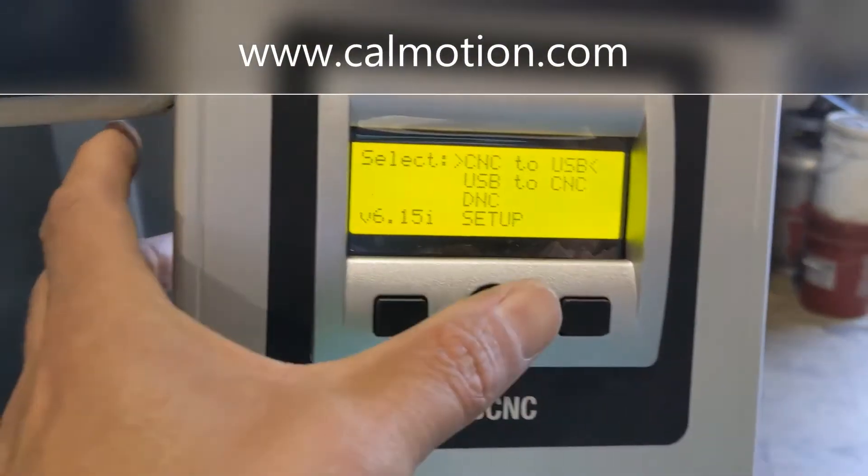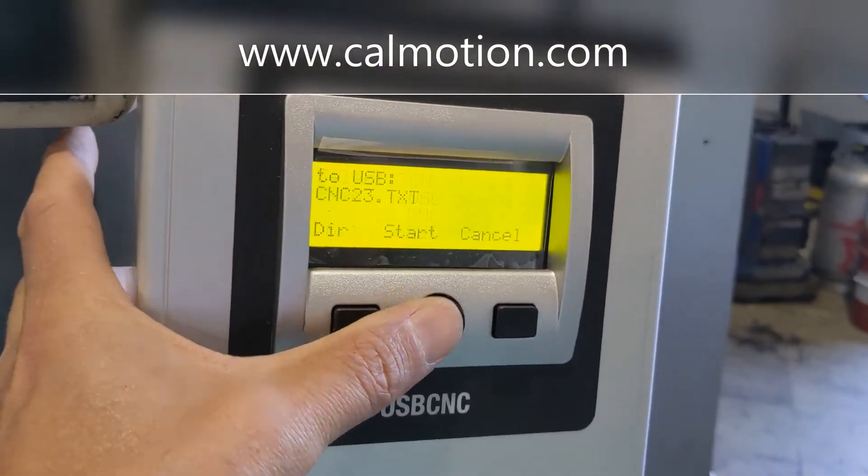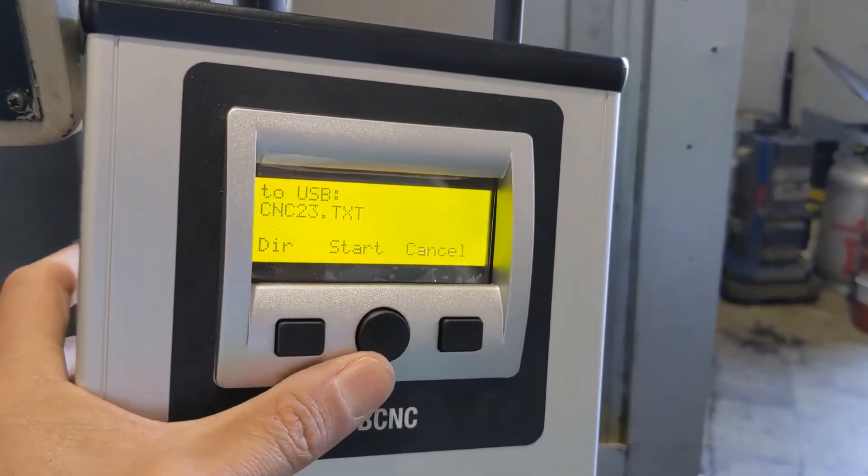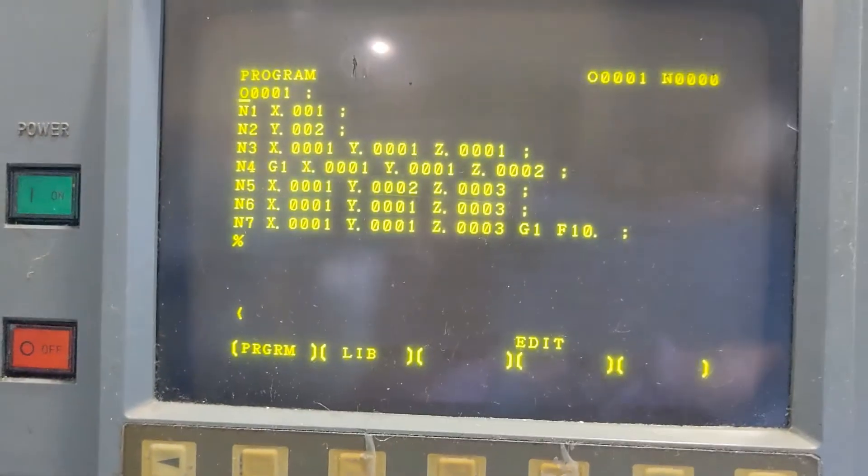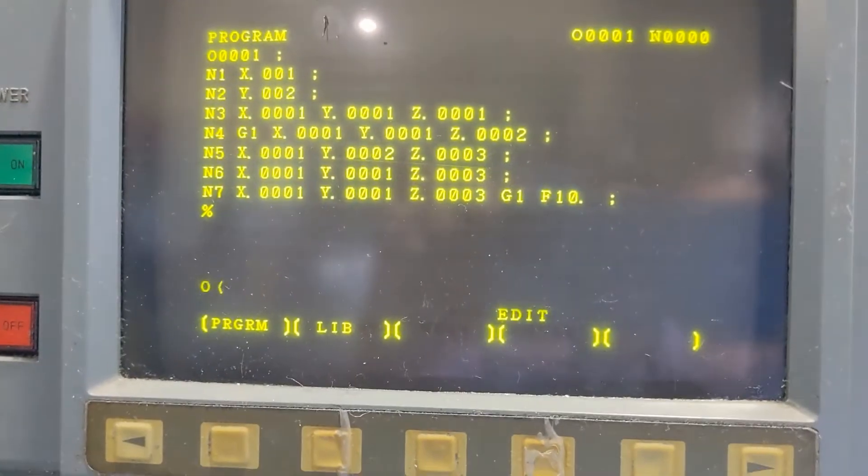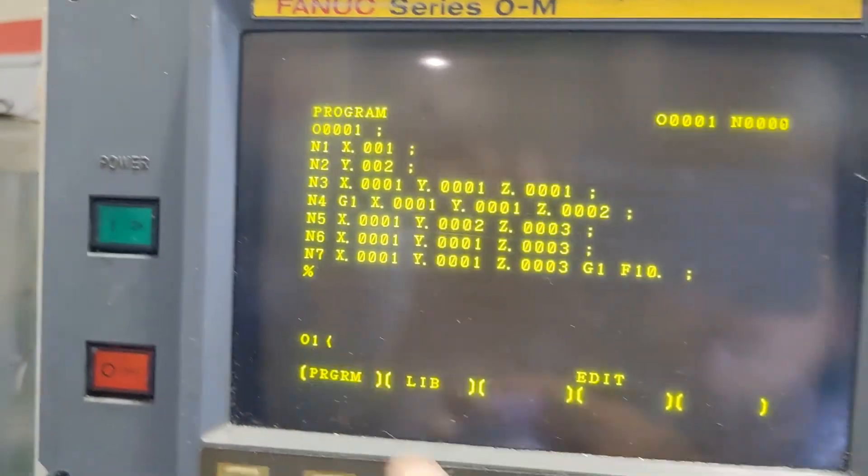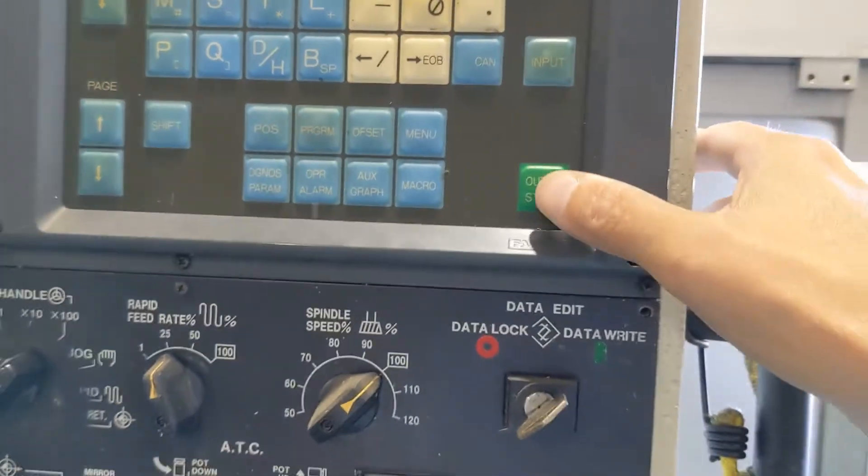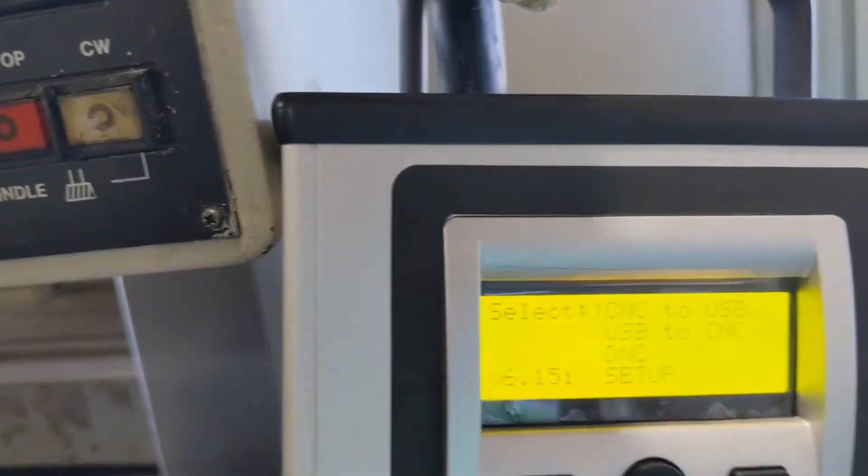You select CNC to USB, select start, and now it's ready to go. On the FANUC, you'll select the program you want to send. We want to send 01. You'll see the 01 here. When you have that, you'll press the output start. And on the box, you'll see that the orange light blinks and it's received that file.